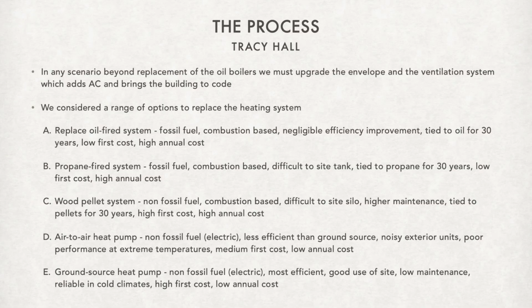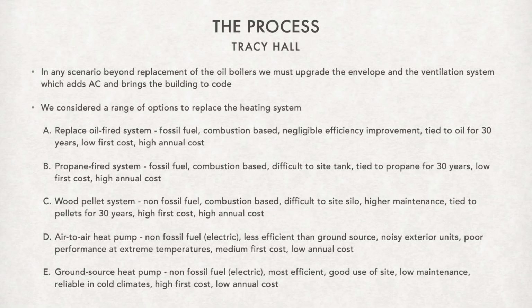The disadvantages of an air-to-air heat pump: it's a relatively expensive system, maybe a little cheaper than our last option, but not much. The exterior units remain or become larger, and there may be more of them. Air-to-air heat pumps are not particularly high performing at extreme temperatures, because in the summer you're trying to dump your heat into the hottest possible air, and in the winter you're trying to draw heat from the coldest possible air. So it's not the most efficient. First cost is a little less than our last option, similar to the others, but it does have a low annual cost because it's relatively efficient energy-wise compared to combustion systems.